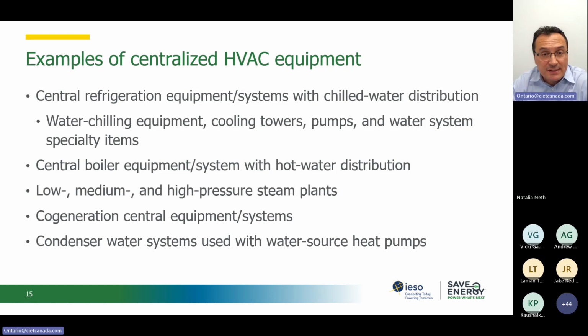In older buildings, we may even see steam in some places, although in many cases we convert this energy from steam to hot water before we distribute it in the building. One example that's still used in many central plant systems on university campuses or hospitals is a central steam plant, and then distributing the heat inside, let's say to a residence building on a campus, a multi-unit residential building, using hot water after we convert the heat from steam to hot water.